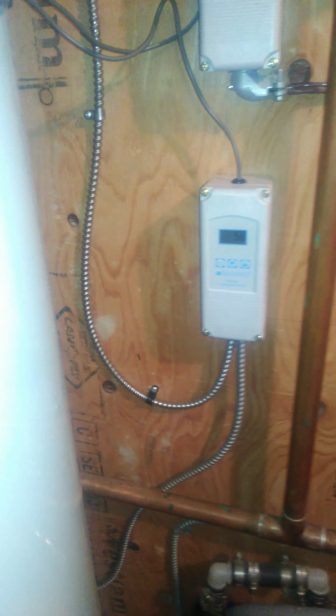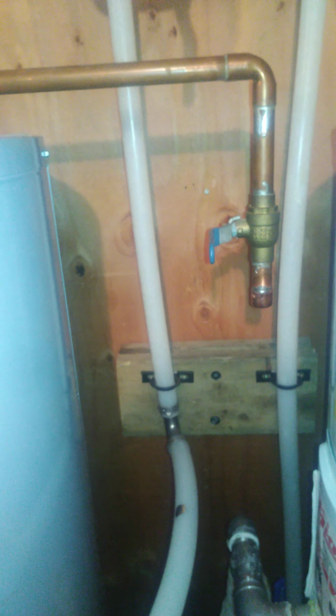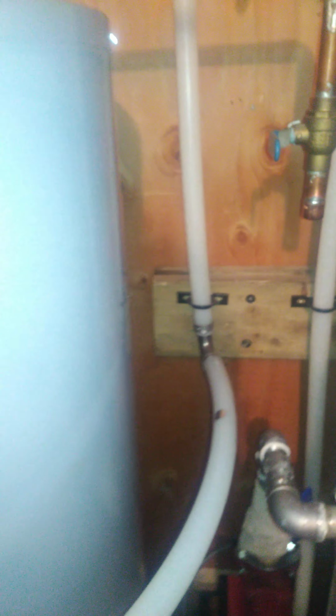So what I've done is offset these two temperatures. I've changed the aquastat for the boiler and set it at 130. What will happen is, because this water's coming down that supply line at 180 degrees, and for the most part I don't want to run 180 degrees in my infloor.